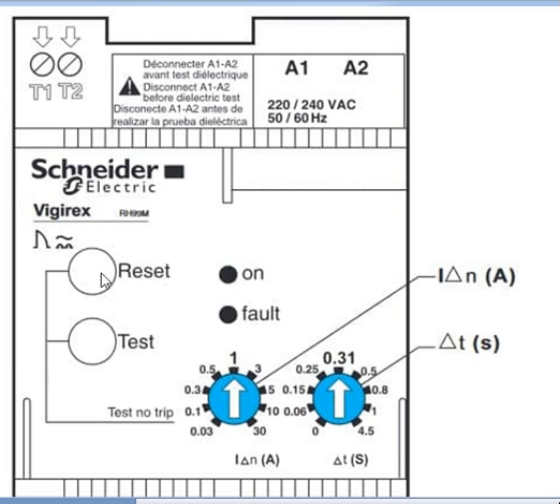And friends, there will be one reset button on the top of the relay. If there is any fault in the relay, you can reset it from the reset button, and you can test your relay as well, whether it is working or not and whether it is going to energize the protection relay or not. You can test your relay by pressing the test button. Once you press the test button, it's going to trip the circuit, and like that you can do the test.